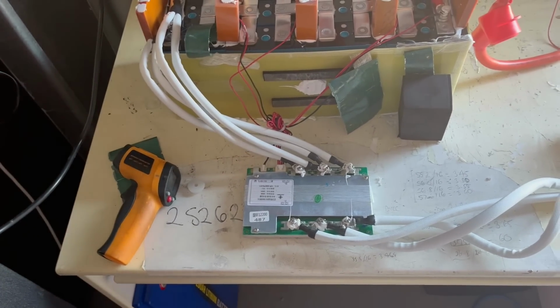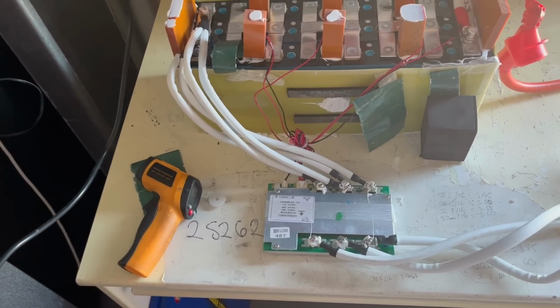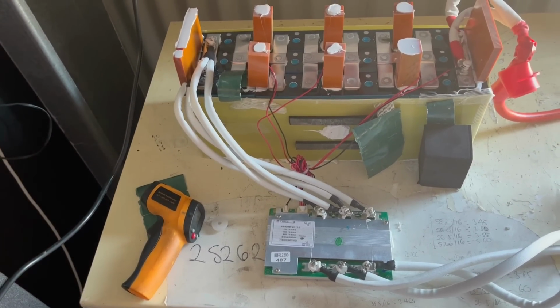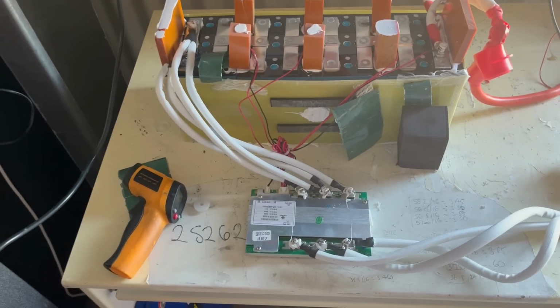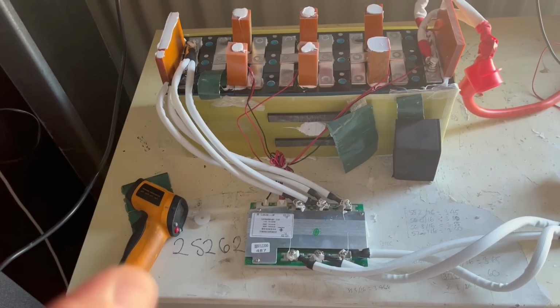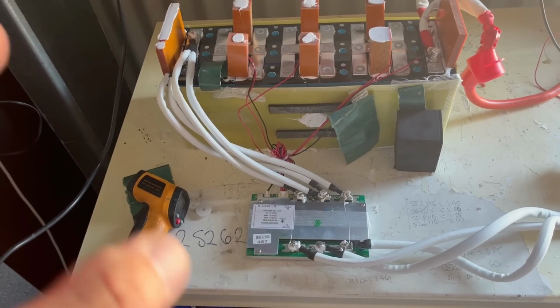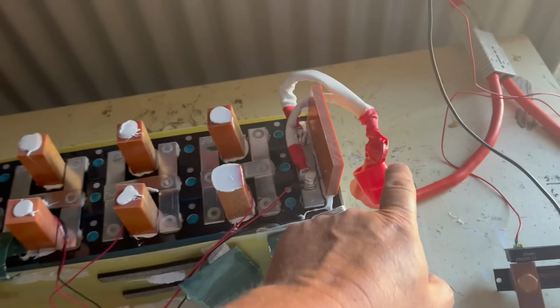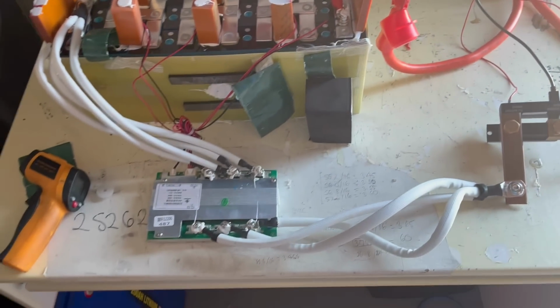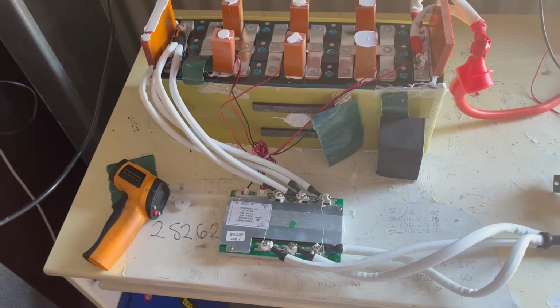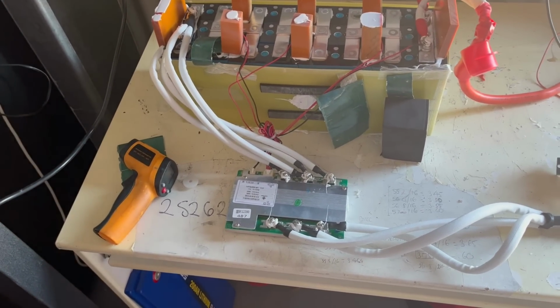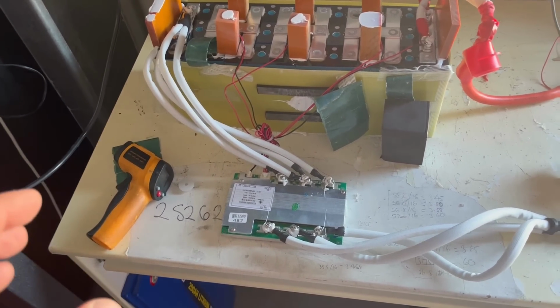Now, it put out just under 200 amps. It was, what was it, 197 on one discharge and then 198.6 or something on the other. Unfortunately for me, this battery is a fail simply because of that positive terminal and the way it heated up. Quality just isn't there. It was moving in the back of the casing, and I showed you guys that clearly a minute ago.